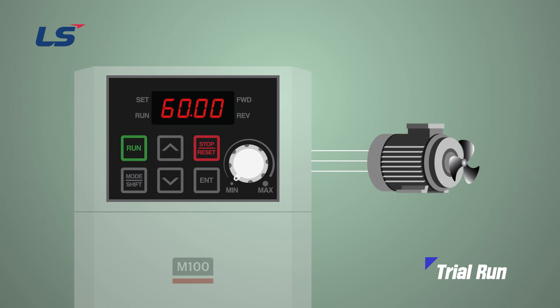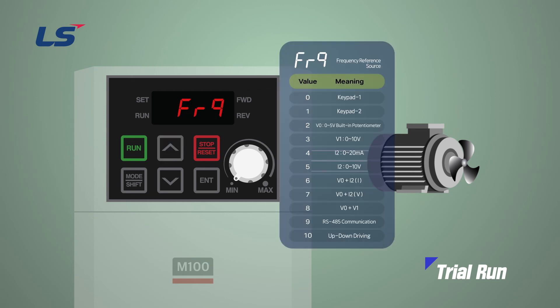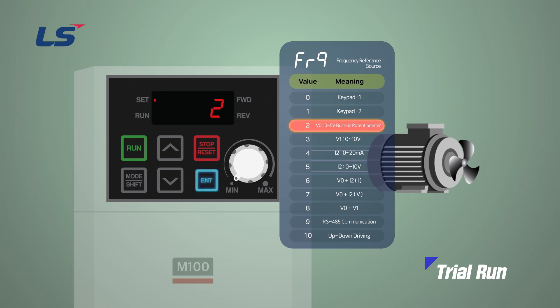Use the up and down arrow keys to navigate to the frequency parameter, and change its value to 2, which corresponds to the built-in volume on the right side of the M100 keypad. Set to 2 to continuously change the target frequency with the built-in volume.